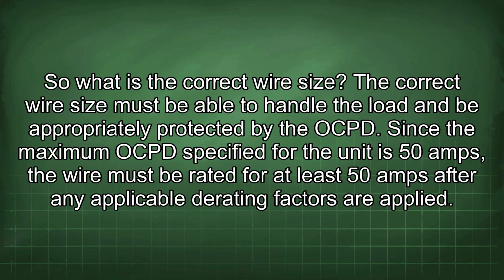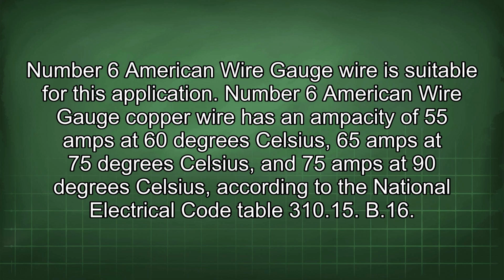So what is the correct wire size? The correct wire size must be able to handle the load and be appropriately protected by the OCPD. Since the maximum OCPD specified for the unit is 50 amps, the wire must be rated for at least 50 amps after any applicable derating factors are applied. Number 6 American wire gauge wire is suitable for this application. Number 6 American wire gauge copper wire has an ampacity of 55 amps at 60 degrees Celsius, 65 amps at 75 degrees Celsius, and 75 amps at 90 degrees Celsius according to the National Electrical Code Table 310.15(B)(16).